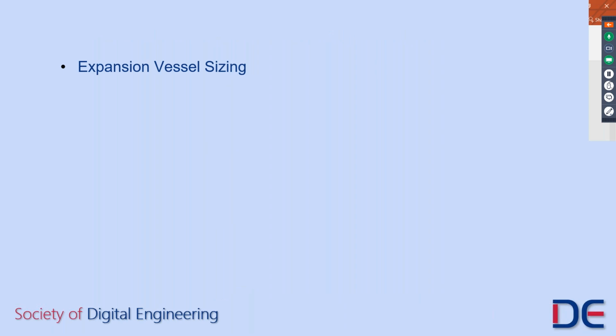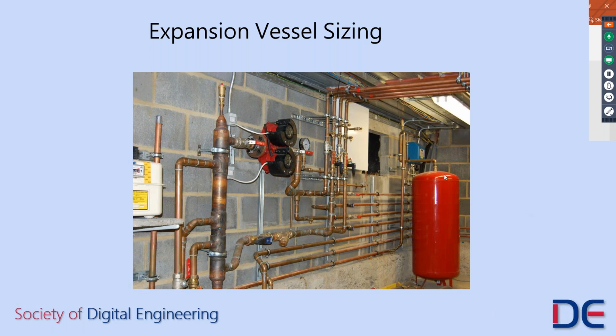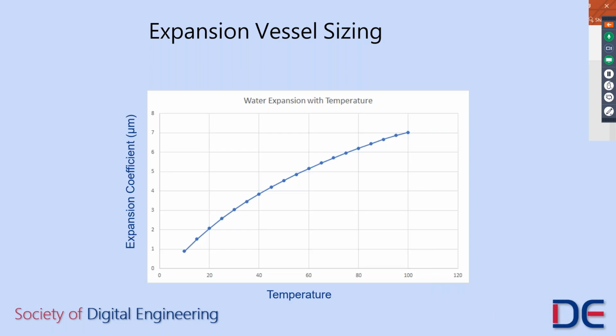Now let's have a quick look at some expansion vessel sizing. We can see here on the right hand side of the image, the expansion vessel can be a quite significant part within a plant room. So it's important to make adequate space for it. To understand the space that's required, we need to work out how much expansion volume is going to be created within our systems. But water is a bit awkward because it doesn't expand in a linear way like most other materials.